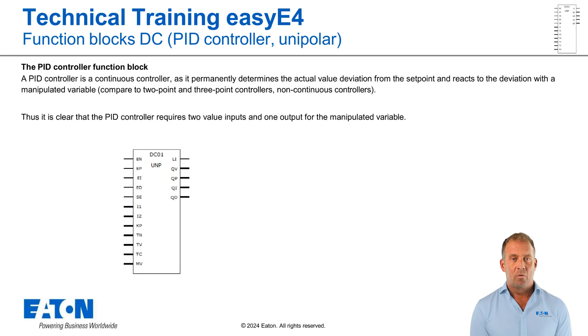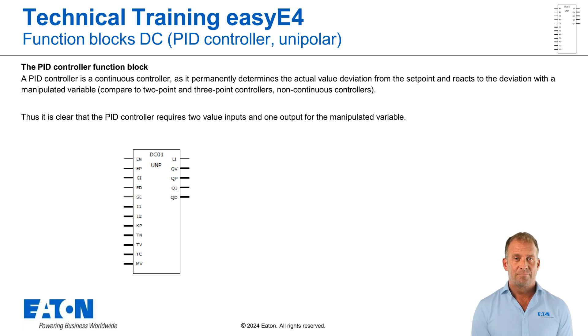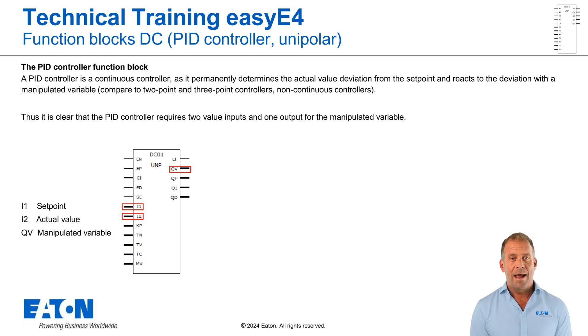The PID controller is one of the continuous controllers, as it permanently determines the actual value deviation from the setpoint and reacts to the deviation with a manipulated variable. This manipulated variable then acts on the control variable via an actuator. The function block requires two analogue inputs for the setpoint and the actual value, I1 and I2, and an analogue output for the manipulated variable, QV.